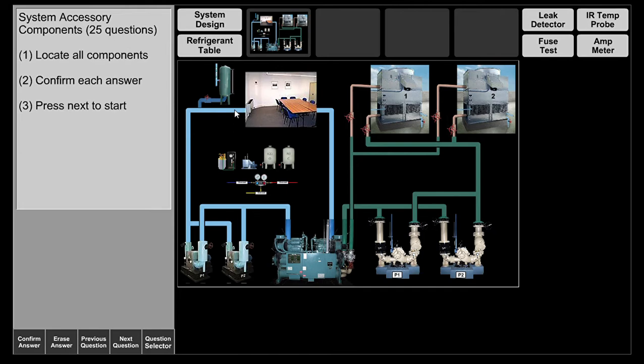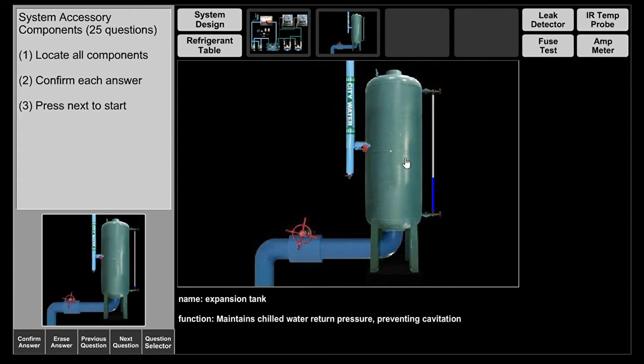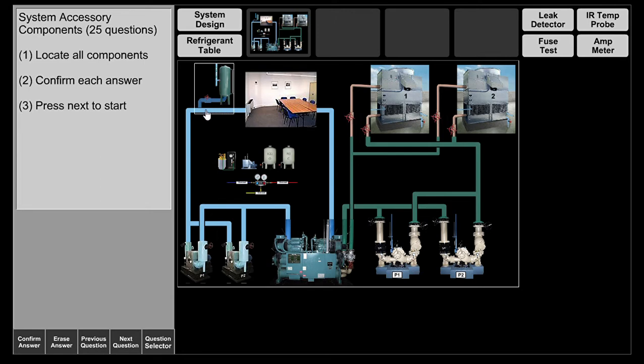As the water travels back to become 45 degrees again, it passes by an expansion tank. This expansion tank serves two purposes: it allows makeup water to be added to the system in the event of a drain-down or leak, and inside it contains a diaphragm with a rubber bladder that maintains constant pressure, allowing the system to work optimally despite any pressure increases or decreases.